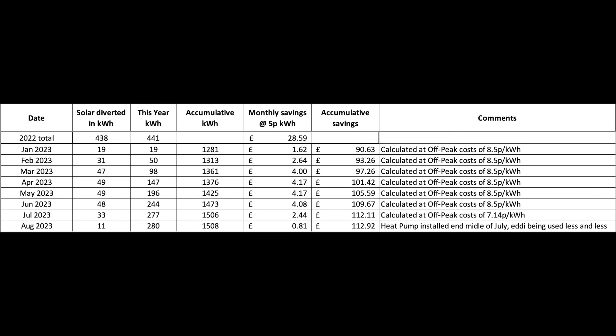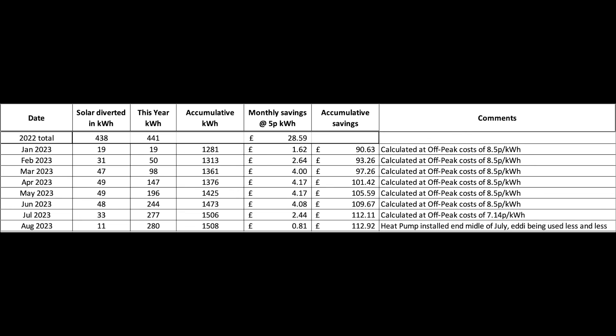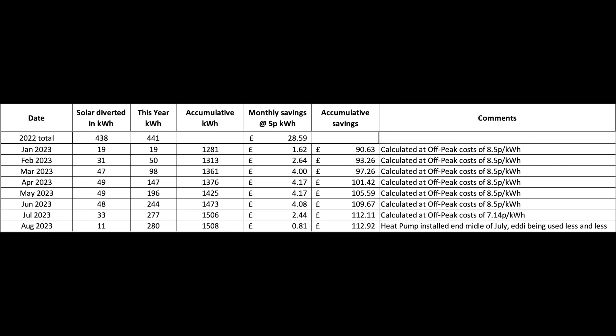This is the Eddy. The Eddy is sort of not decommissioned per se, but it's being used less and less. Because we have the heat pump it's far more efficient to use it to generate our domestic hot water — it's running at a COP of 3.5, so for every one unit of electricity we generate 3.5 units of heat, whereas the Eddy will only ever do one to one. We are using it a bit if we've got loads of excess solar and need to dump it somewhere — into the hot water storage tank. Cars will be first priority, battery second priority, and then if there's nothing else — run the washing machine, dishwasher — I'll heat the hot water with it. So it's not redundant but it's being used less and less.